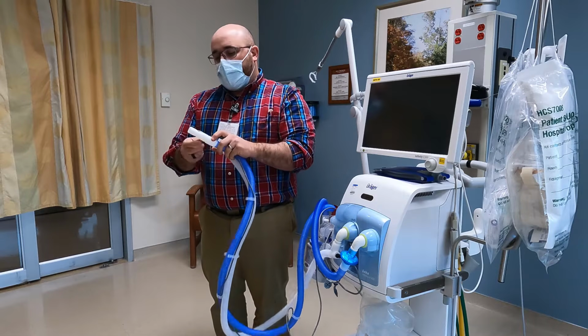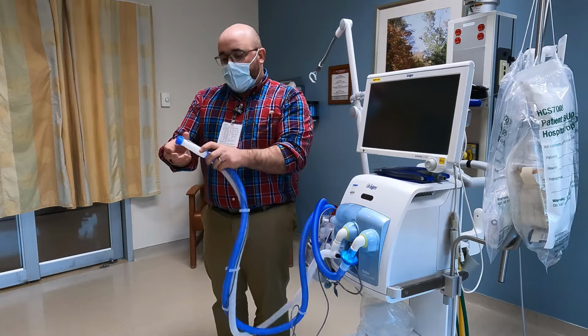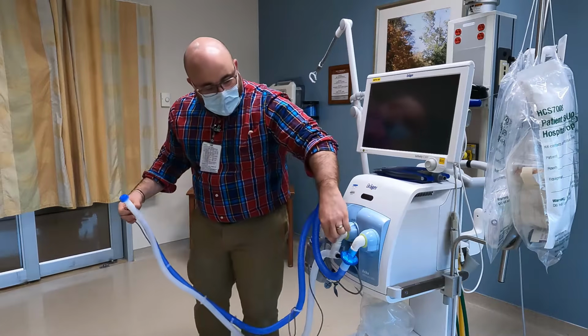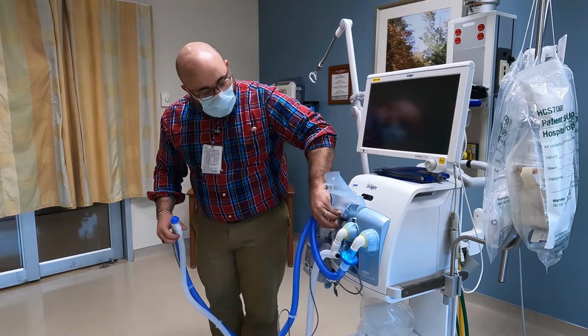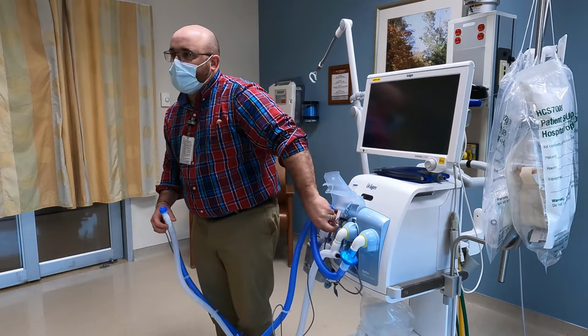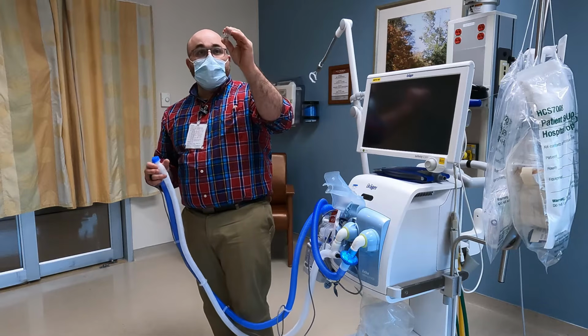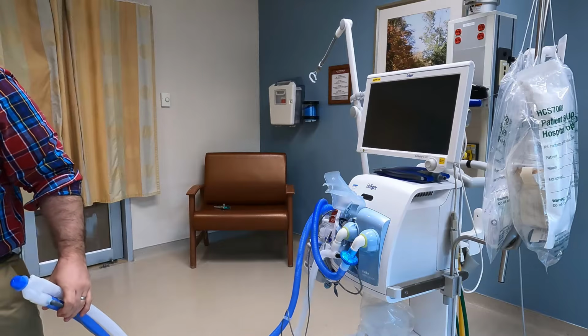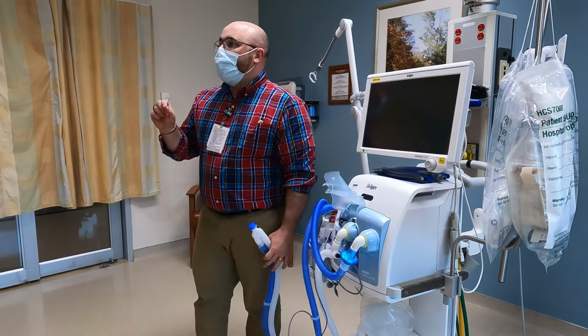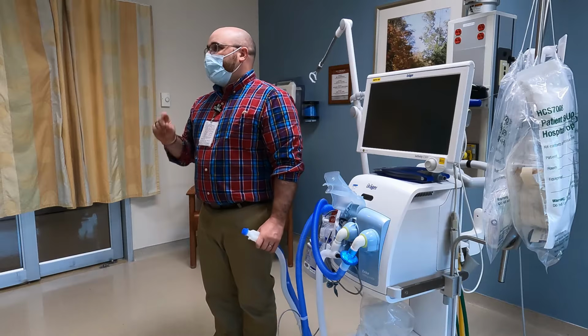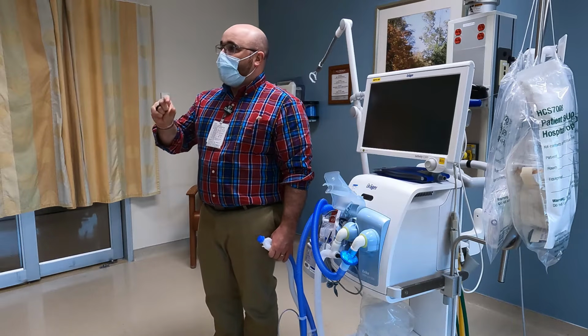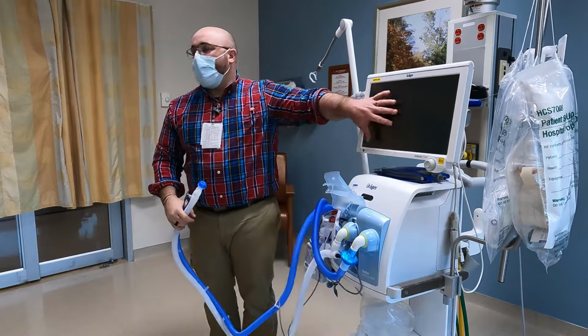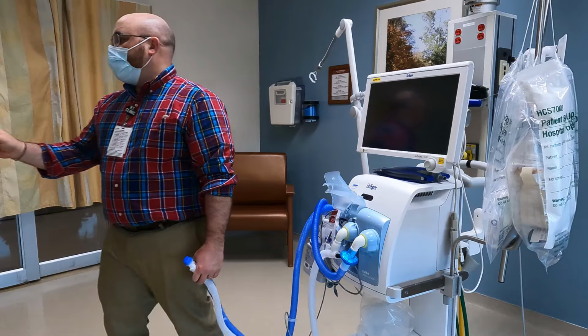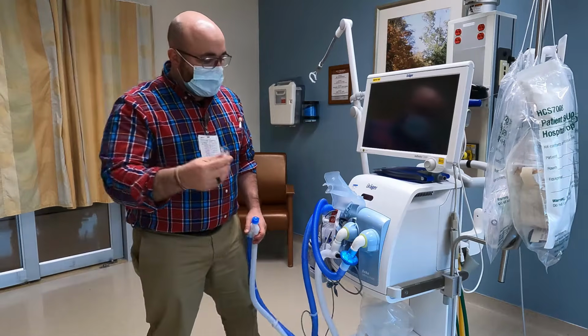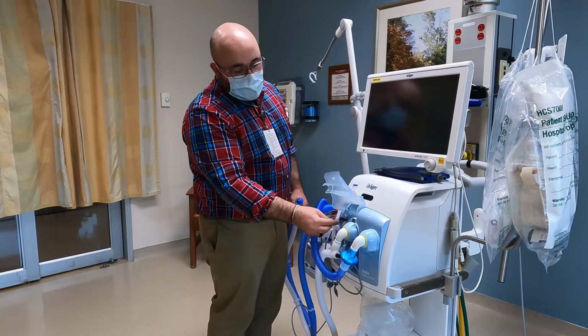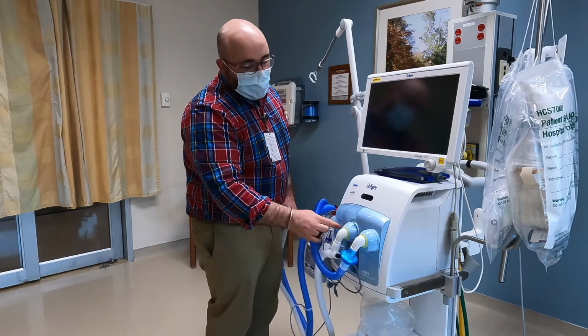So it hooks to a piece of corrugated tubing and to a piece of suction, and then the expiratory side comes straight back into here. Inside this is a little piece called a flow sensor. It has two extremely small wires. You can check those out if you hold them up to the light. That is where every bit of our patient values come from. Those two wires are heated to a specific temperature. When the air flows by them, that's what gives you all the stuff on the screen. As you can imagine, these get broken and they stop working, so we have to put new ones in. These are reusable. So anyway, this is an important area because you have to get that air coming out.